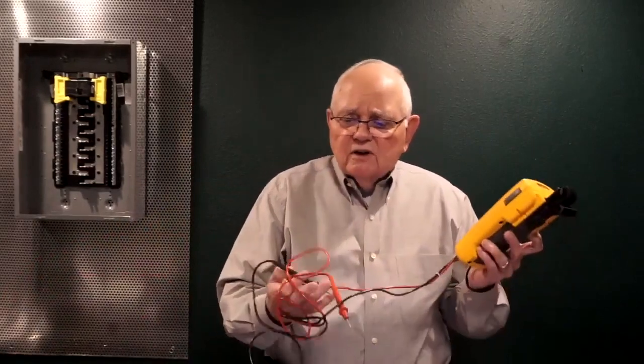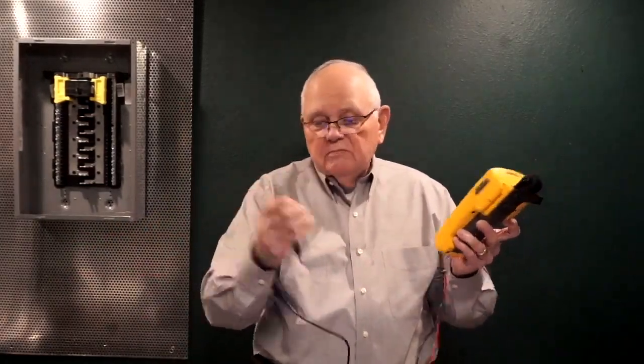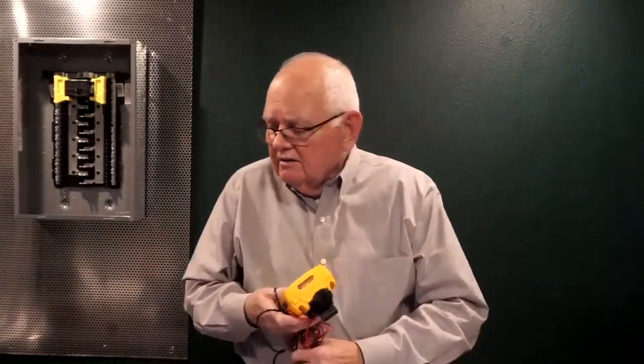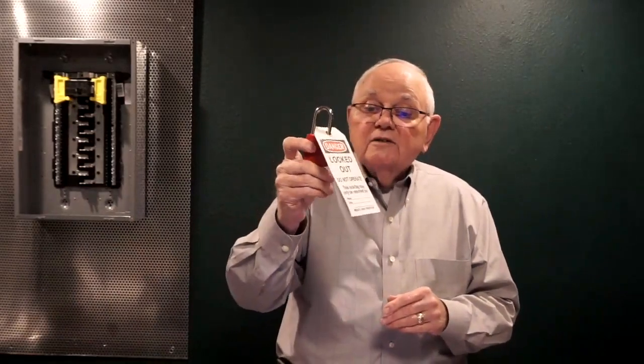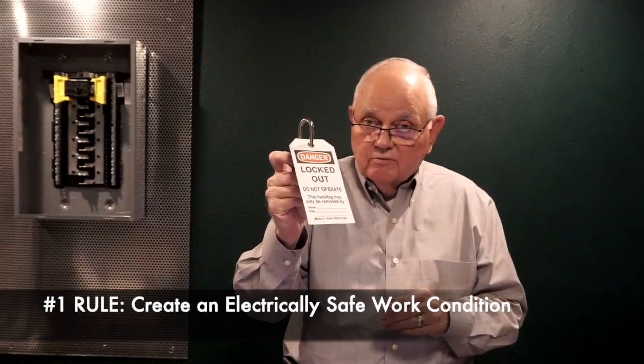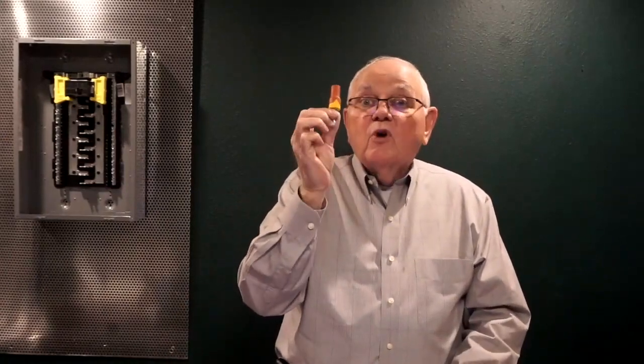If you think about it, even the test leads on our meter are insulated to 1,000 volts. So lots of protection out there for us from electric shock. First of all, we want to lock out and tag out. Number one rule, lock out and tag out. Create an electrically safe work condition. If I still have to do work on energized equipment, follow all of my safety rules, use my hierarchy of controls, it's called, in the NFPA 70E standard. Wear my insulated rubber gloves, my PPE, to protect me from electric shock. And finally, as secondary protection as well, use insulated tools that are properly rated.